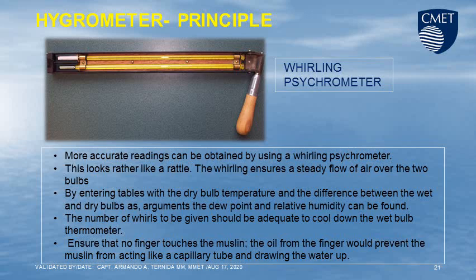From the readings, the dew point and relative humidity can be found. The number of rotations given should be adequate to cool down the wet-bulb thermometer. Ensure that no finger touches the muslin, as the oil from a finger would prevent the muslin from acting like a capillary tube and drawing the water up.